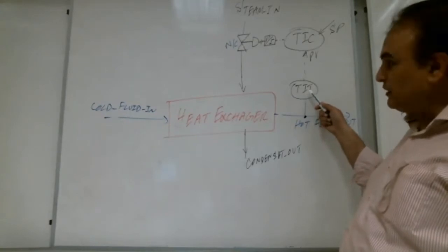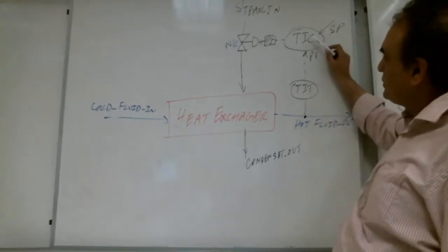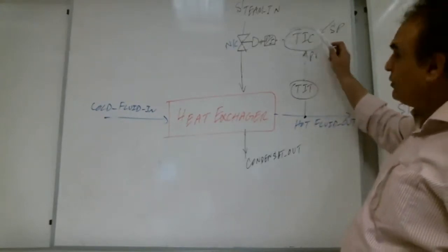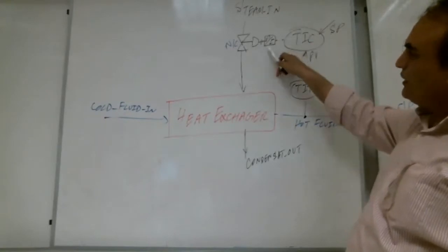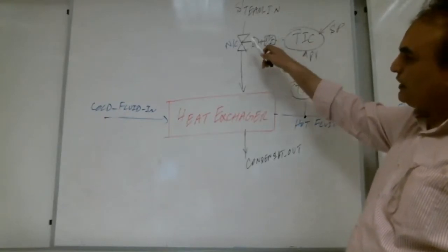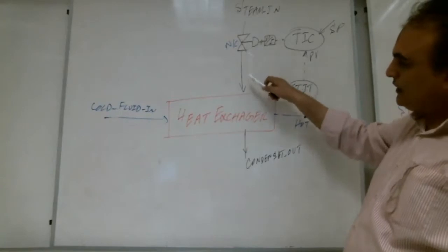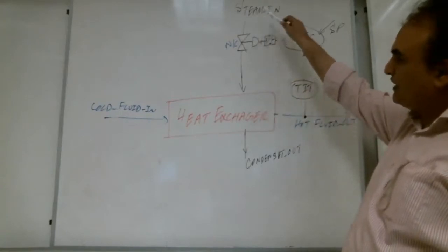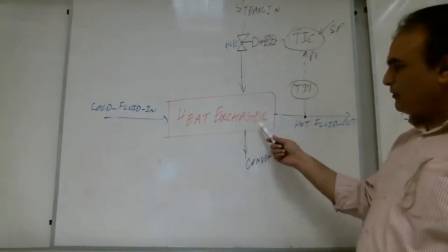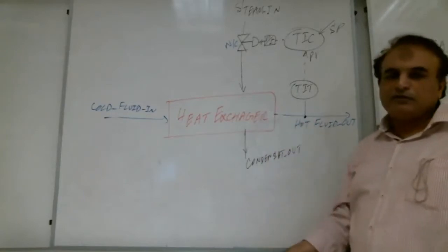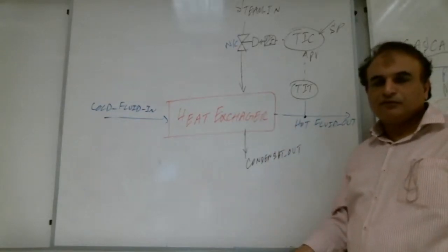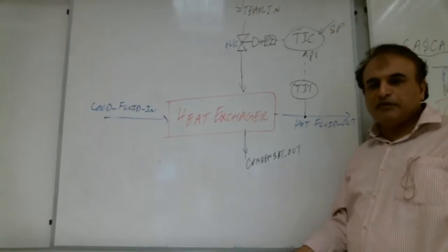It will go to the transmitter. The transmitter will send it to the controller. Then the controller will decide, then it will send to the I2P converter, then to the valve, and the valve will open more and steam will come. Meanwhile, how much fluid has been lost? How much fluid has been lost, Shabab, meanwhile?